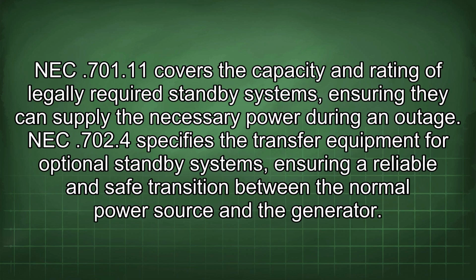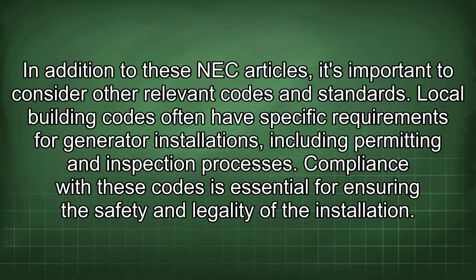NEC 701.11 covers the capacity and rating of legally required standby systems, ensuring they can supply the necessary power during an outage. NEC 702.4 specifies the transfer equipment for optional standby systems, ensuring a reliable and safe transition between the normal power source and the generator. In addition to these NEC articles, it's important to consider other relevant codes and standards. Local building codes often have specific requirements for generator installations, including permitting and inspection processes.